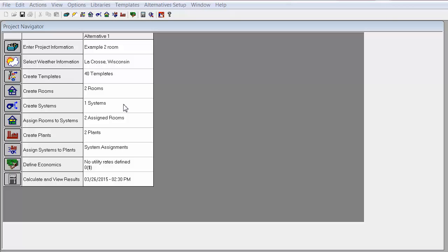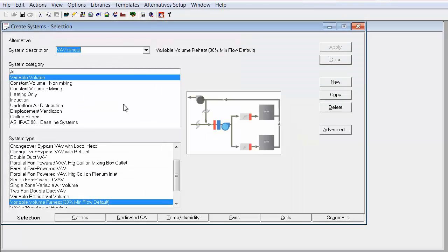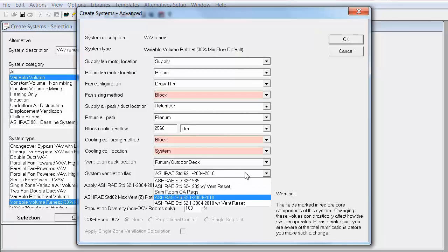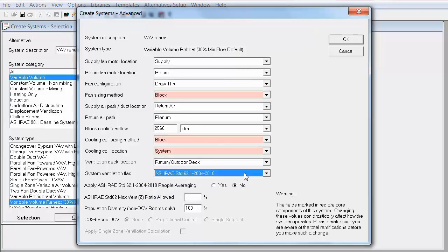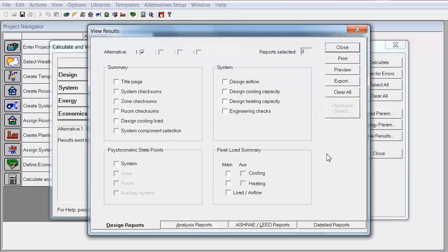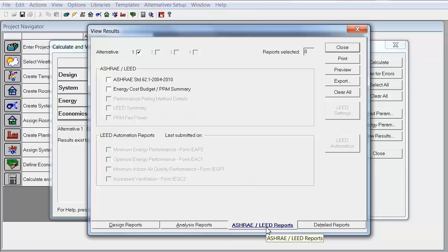The second step in applying 62.1 in TRACE 700 is to select the ASHRAE 62.1 flag in the Create Systems Advanced window. This step is very important, and if not applied, TRACE will not provide an accurate calculation of the outdoor air flow rate. After you run your analysis with 62.1 applied in both the rooms and the system, there will be a 62.1 report available that reports the calculation results with all the 62.1 parameters laid out.